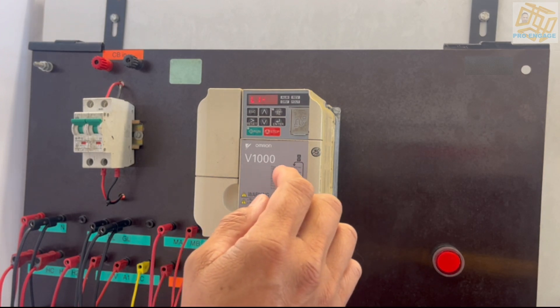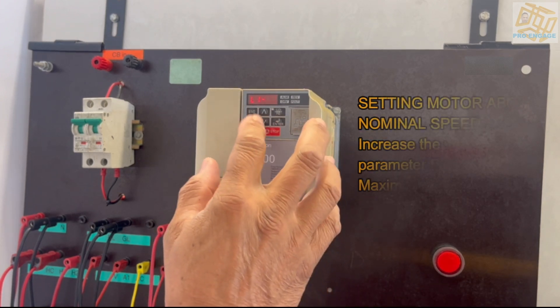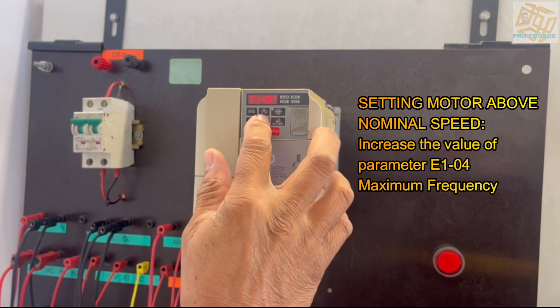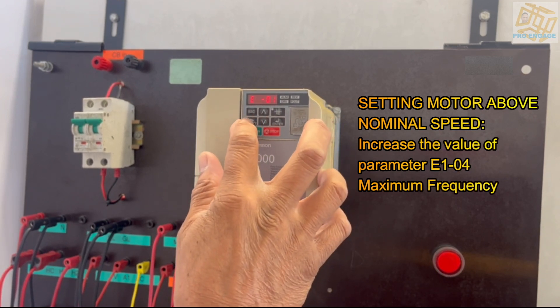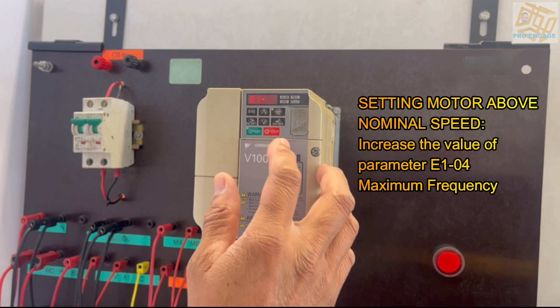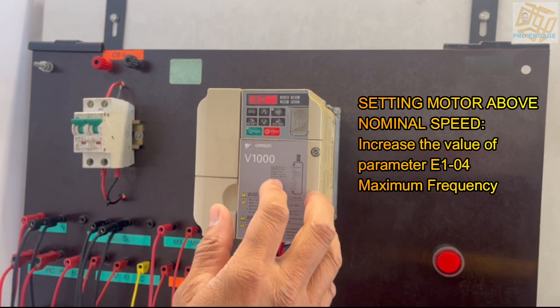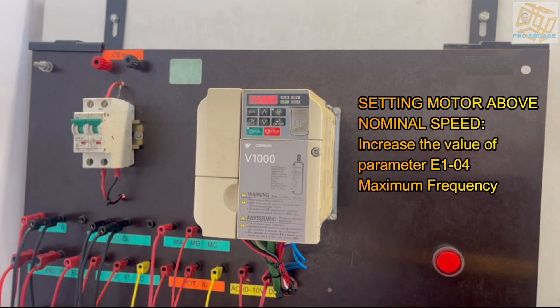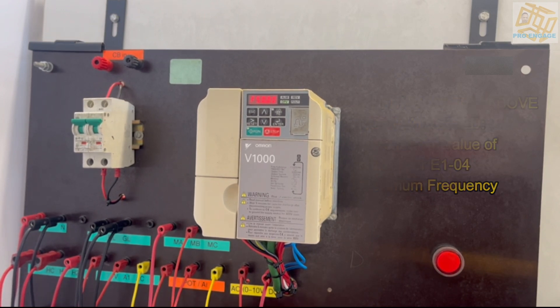There is the motor setting, motor above nominal speed. This would be one of the final settings. Increase the value of parameter E1-04 maximum frequency. If you set it to 40 hertz then the maximum will be 40 hertz. In this case it's 50 hertz, so this motor would run at maximum 50 hertz. We're changing the frequency so the motor will slow down or speed up. This has brought us to the end of setting the parameters.